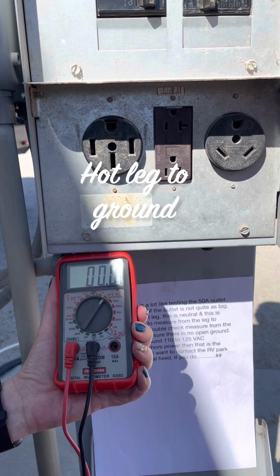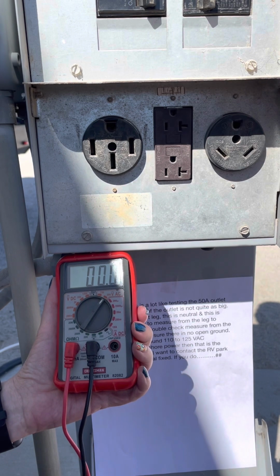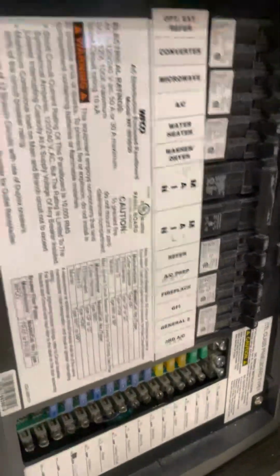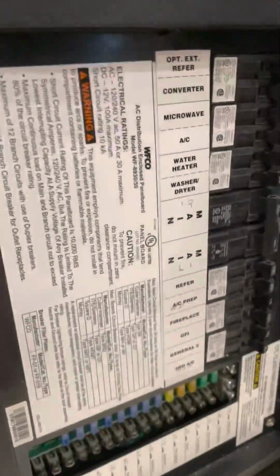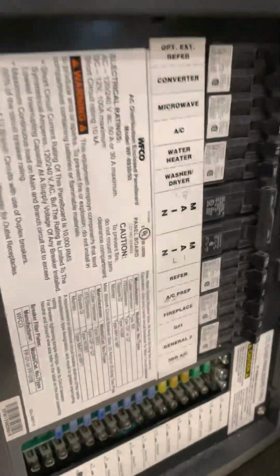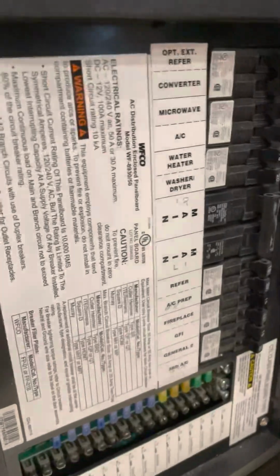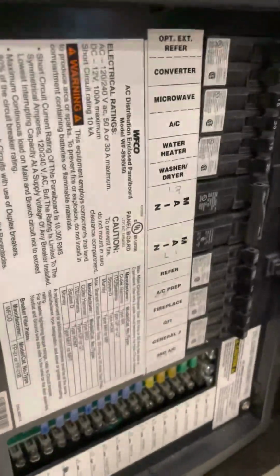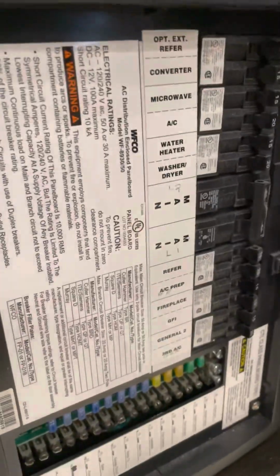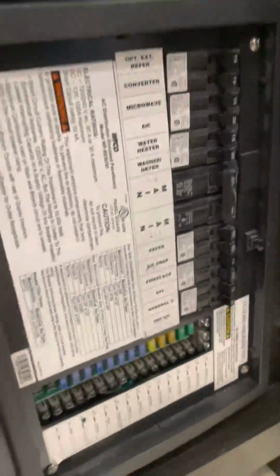If any of these test poorly or not correctly or less than 120 volts, then you'll need to contact the RV park and have the pedestal fixed. If you do have a good pedestal, if everything checks out at the pedestal, if you have power coming from the pedestal to your RV, next thing you need to do is verify that you actually have power inside the RV. Go to your main panel.